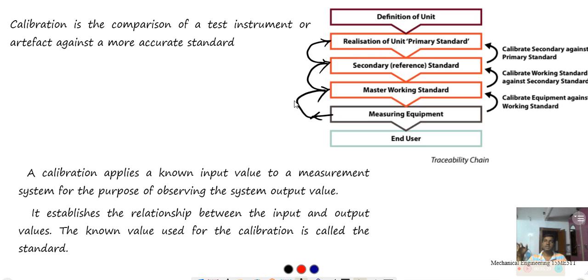If the first time it indicates 1 kg, and the second time it indicates 1.1 kg, it means there is no repeatability. Repeatability is not there, so we want to calibrate it. Some of the parts are not working. There will be backlash, there will be hysteresis, there will be friction. All those things are going to occur, or wear and tear will happen. So that is going to be calibrated. All these things come under the picture of calibration.